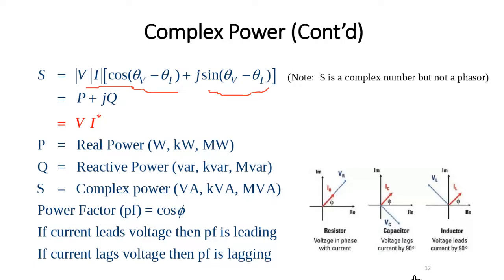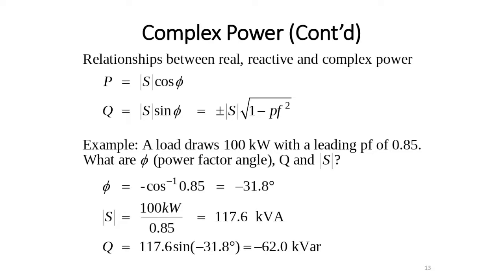Okay, so if you're using power factor 1, for example heaters, Kahrama is happy. But if you're using heavy industry, for example heavy motors, well, Kahrama will not be happy. So you need to install capacitors. The factories install capacitors to compensate for the reactive power, as we will discuss the compensation later.